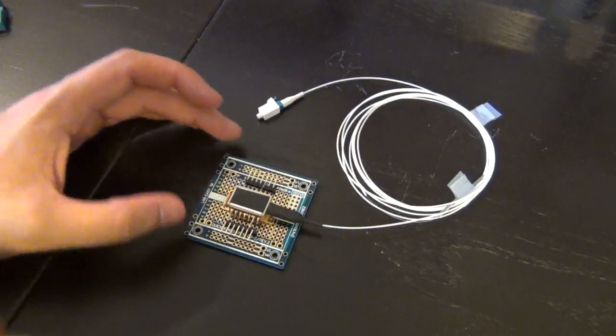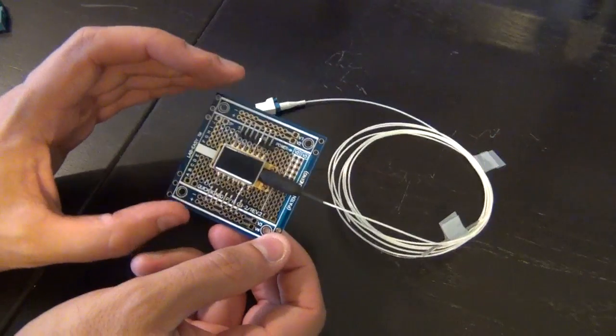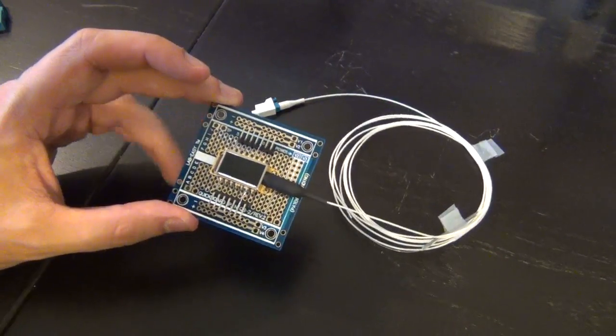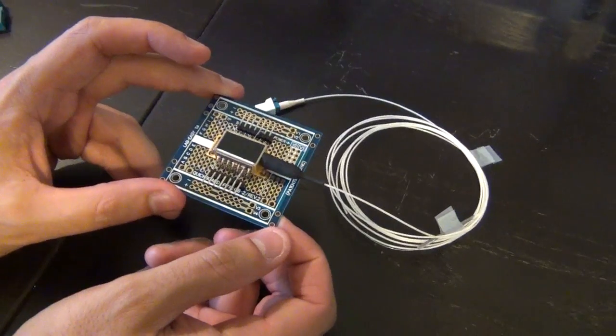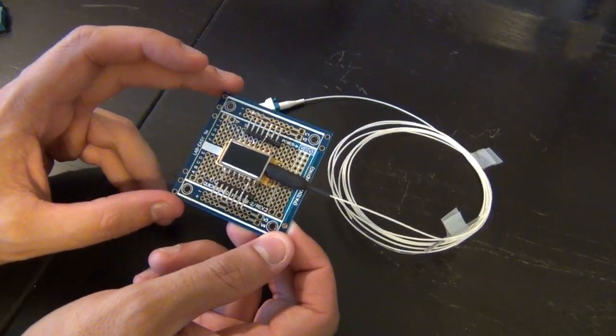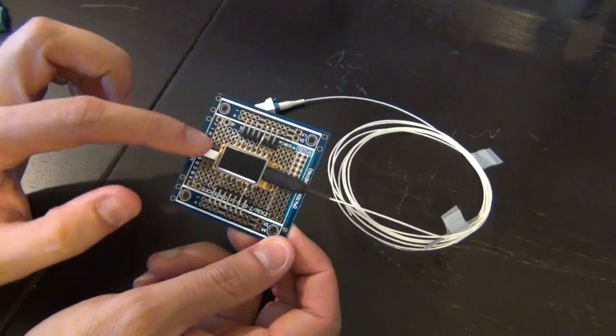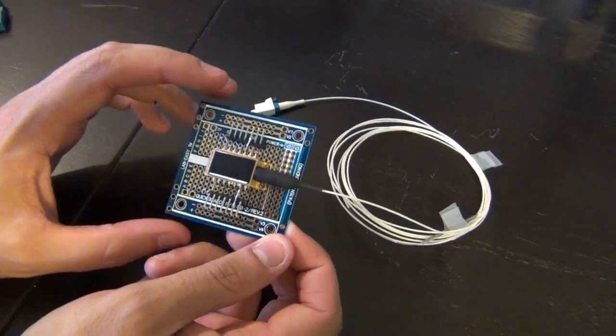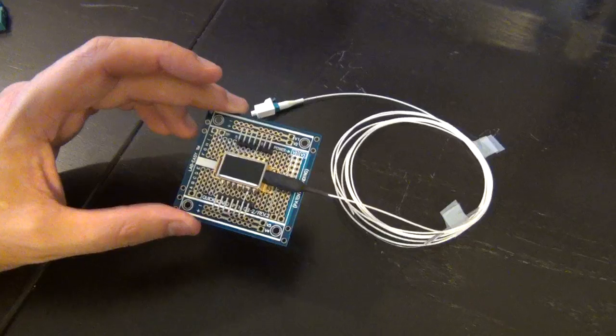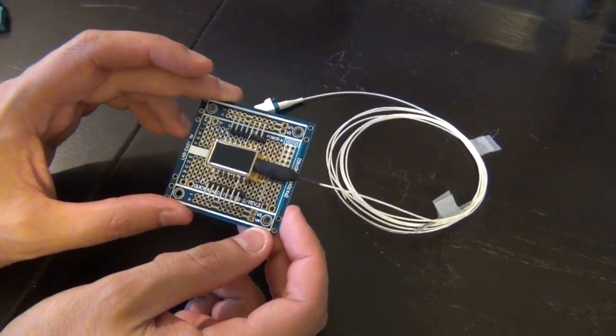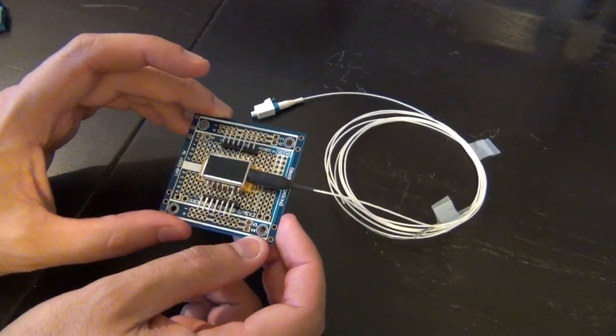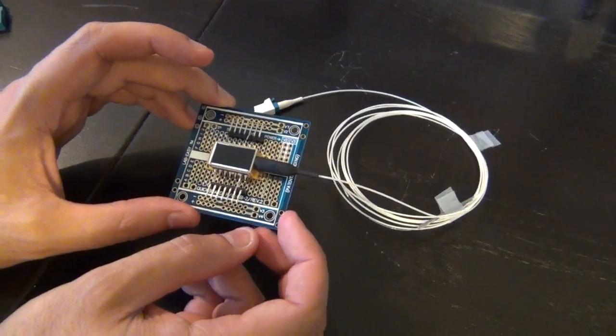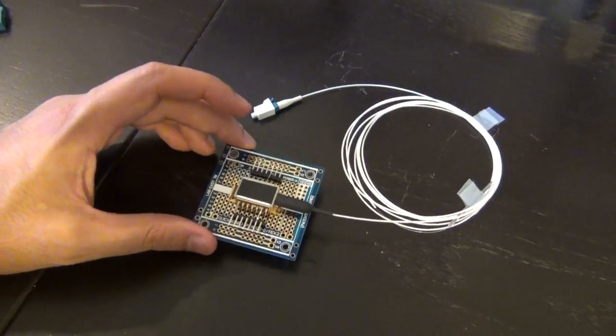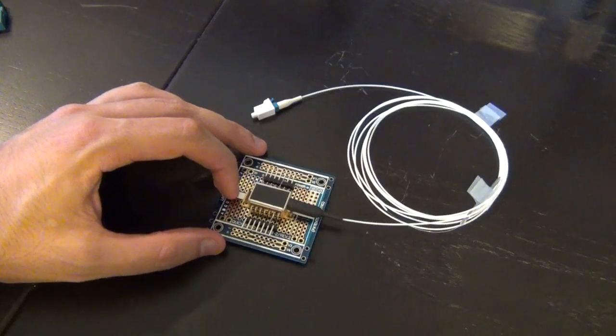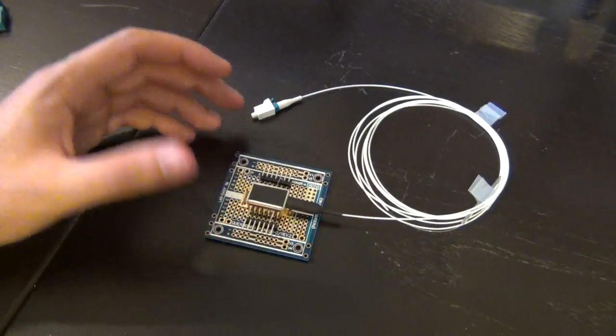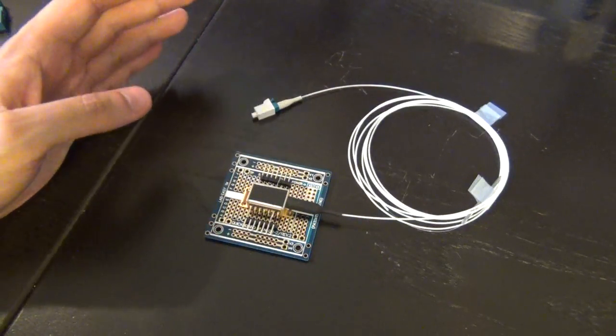So to test the wavelength meter, I'm going to use this laser module. Now inside this little package is more than just the laser diode itself. There is also a modulator, there's temperature control loops, there is even a solid state cooler built into here. It measures and approximates the wavelength that comes out, as well as the optical power that comes out. All of that is necessary because the laser's center frequency or its wavelength is a strong function of temperature, and it has to be very carefully controlled in a feedback loop in order for you to have a stable laser source.